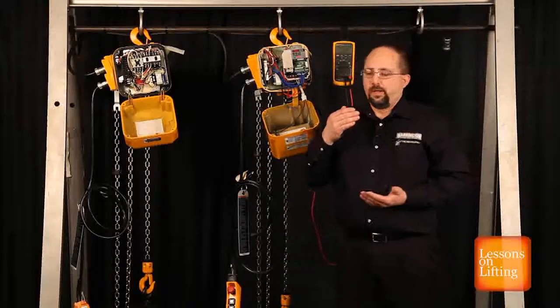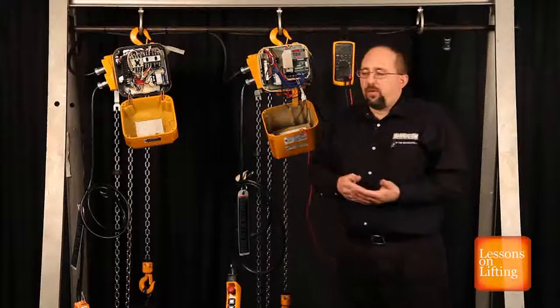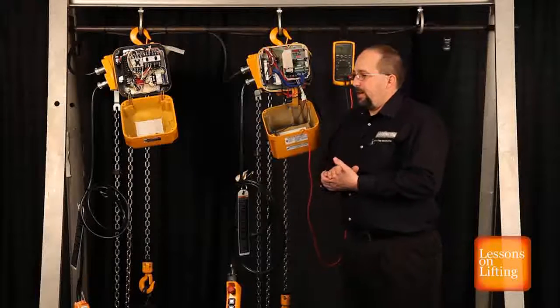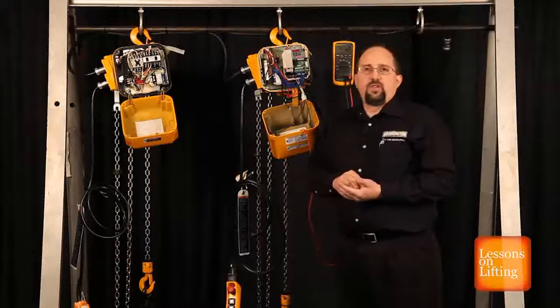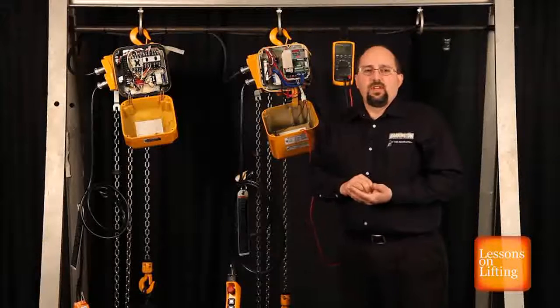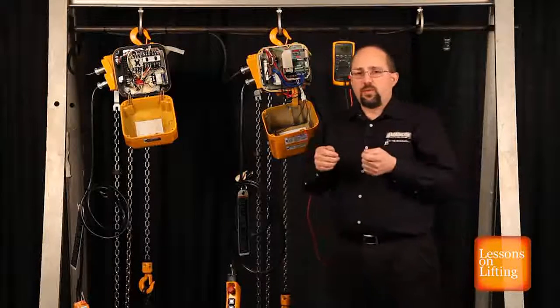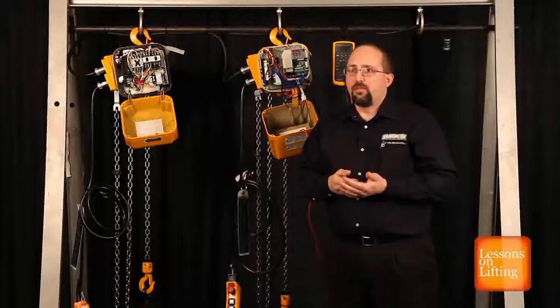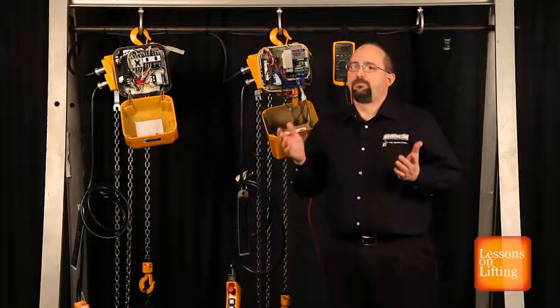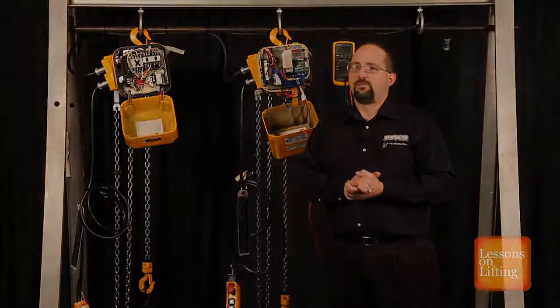There's not control voltage. We thought we had it. If the code goes away with the jumper, it's not the VFD. If you install the jumper between HC and H1 and the code's still there, then you need a VFD.